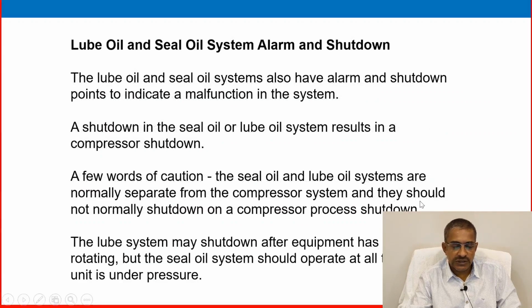So we have checked process, and mechanical we already discussed, and the next one is lube oil and seal oil system, alarm and shutdown. The lube oil and seal oil systems also have alarm and shutdown points to indicate a malfunction in the system. A shutdown in the seal or lube oil system results in a compressor shutdown. A few words of caution: the seal oil and lube oil systems are normally separate from the compressor system, and they should not normally shut down on a compressor process shutdown.